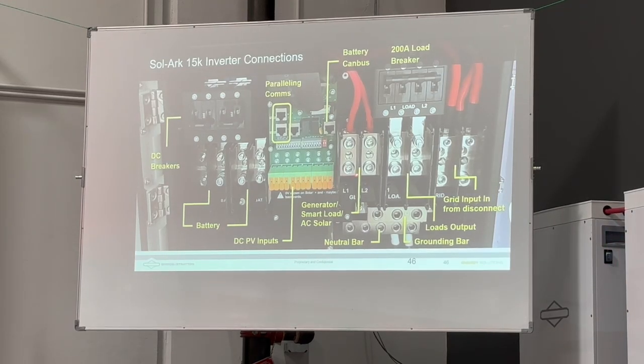All right, then the generator input comes next. The load and grid inputs are 200 amps, so that's 3/0 copper. The generator input is 100 amp limit, so 100 times 240 volts, that's 24 kilowatt max. Really, it's 19 kilowatts of continuous use. So it's derated to about 80 amps of continuous power if you're pulling straight out of the generator continuously.